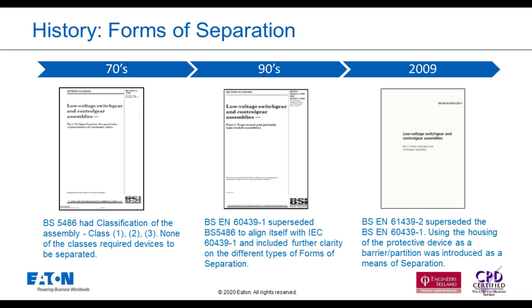Regarding forms of separation, although the British standard adopted the IEC standard forms, there was a big drive from the large users of LV switchgear to provide safer assemblies and give more clarity on the different types of forms of separation. So the large UK manufacturers collaborated and helped form the BEMA guide on forms of separation, and this was added as a national annex to the standard. Then in 2009, the standard updated once again to 61439, and again, regarding forms of separation, the main change was using the housing of a protective device as a means of separation.